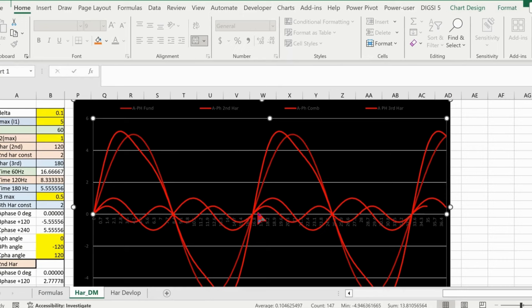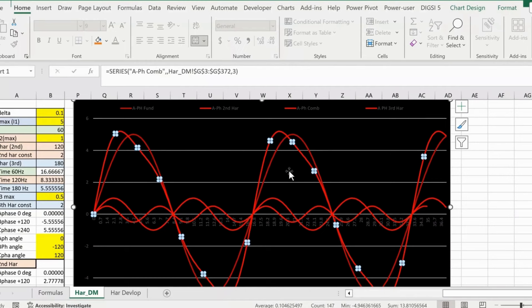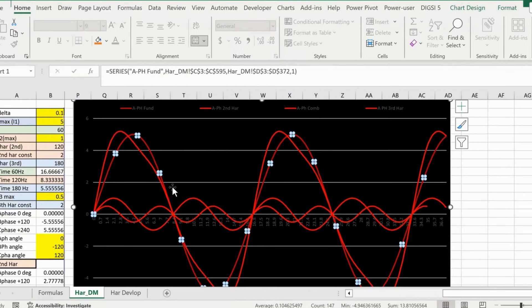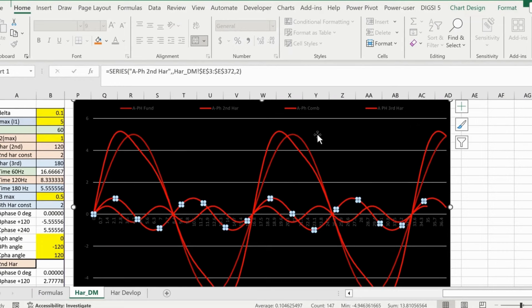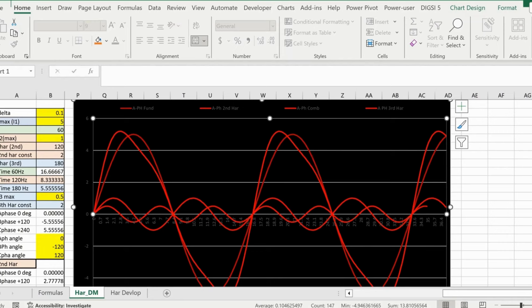Modern numerical relays must understand, measure, and predict the actual fundamental waveform by separating harmonic components. In the old days with electromechanical relays, we used to parallel two frequency waveforms — give a harmonic waveform from one test set output and the fundamental from another, and connect both to the same terminal. Modern relay test kits like SMRT can generate a single output with the superimposed waveform — we'll cover that in a different session using OMICRON software.